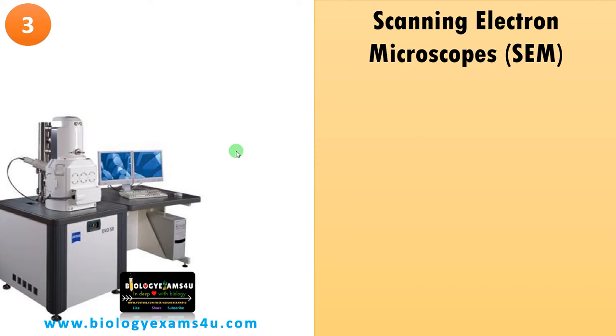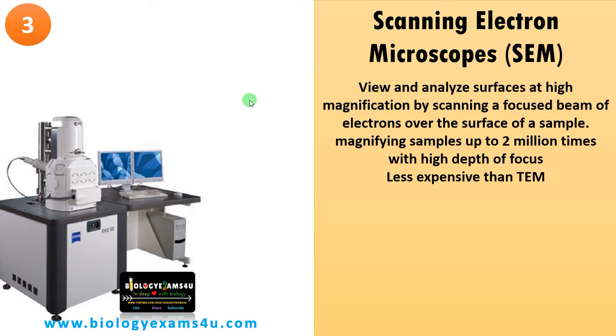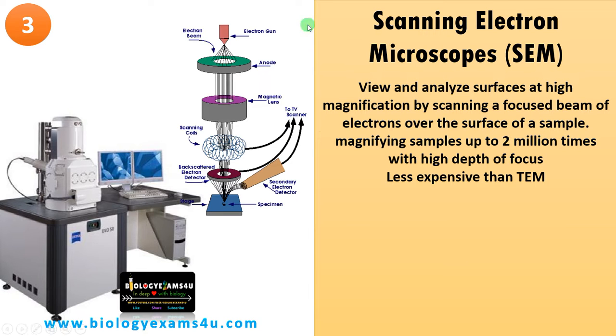Third in the list is the scanning electron microscope (SEM). The illumination source is a beam of electrons. It is used to view and analyze surfaces at high magnification by scanning a focused beam of electrons over the surface of a sample, magnifying samples up to 2 million times with high depth of focus. An electron gun generates electrons, focused through magnetic lenses, with scanning coils directing the beam; secondary electrons scattered from the specimen are detected to create a 3D image.